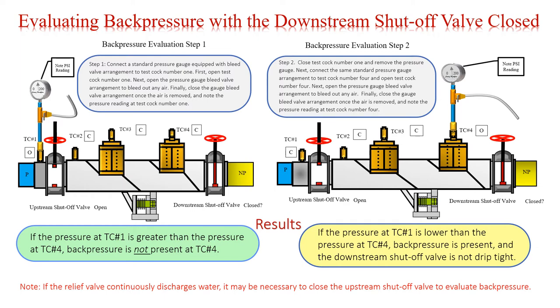Results. If the pressure at test cock number one is greater than the pressure at test cock number four, back pressure is not present at test cock number four. Back pressure is present and the downstream shutoff valve is not drip tight. Note: if the relief valve continuously discharges water, it may be necessary to close the upstream shutoff valve to evaluate back pressure.